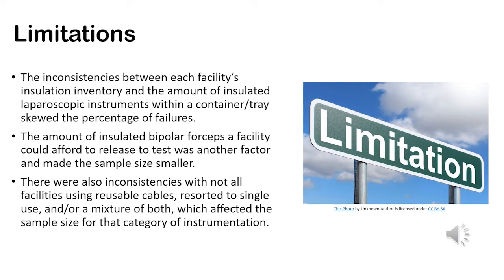Now, for limitations, the inconsistencies between each facility's insulation inventory and the amount of insulated laparoscopic instruments within a tray skewed the percentage of failures. The amount of insulated bipolar forceps the facility could afford to release to test was another factor and made the sample size a little smaller. There were also inconsistencies with not all the facilities using reusable cables and cords and resulted in single use, or they may have a mixture of both, which affected the sample size for that category of instrumentation.